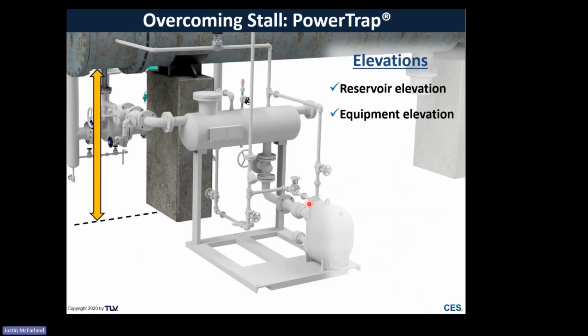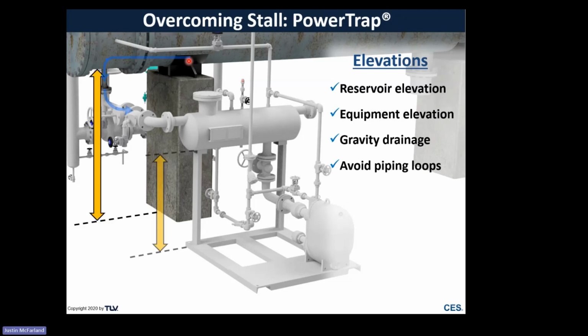Or we've got to make sure we balance that with the equipment elevation, because Chase very astutely mentioned earlier that we need to make sure we're gravity draining from the heat exchanger through, in that example, to a trap, but in this case to the reservoir. We make sure we're balancing the elevation of this reservoir with the elevation of the outlet of the heater to make sure that we're not having to lift up to the reservoir. If we do end up having to lift up, well then we're back in the same situation where we're flooding the heat exchanger and getting all the same problems that we're familiar with, stall. So want to make sure that we've got gravity drainage working in our favor and avoiding any piping loops.